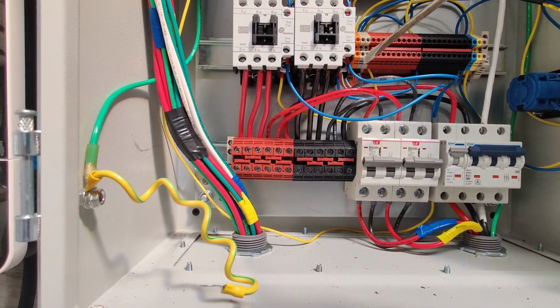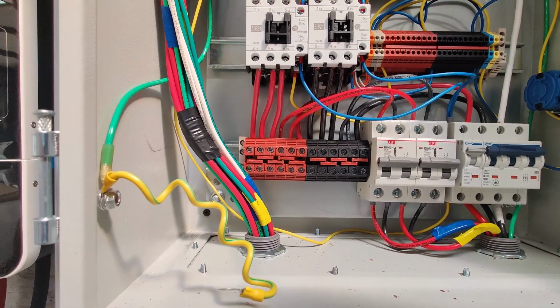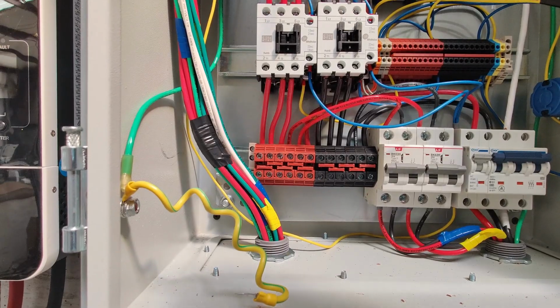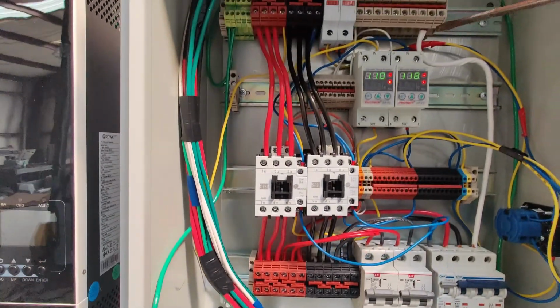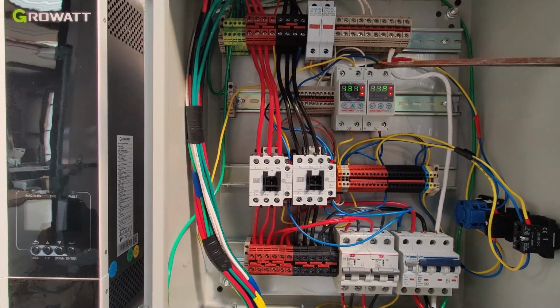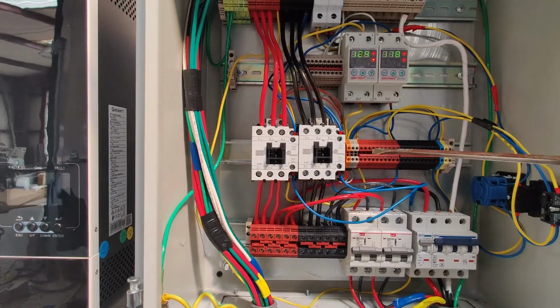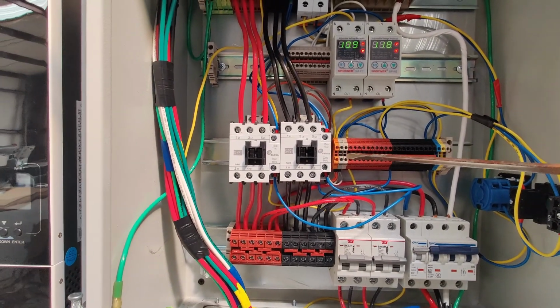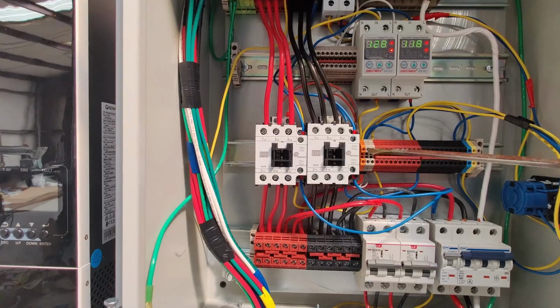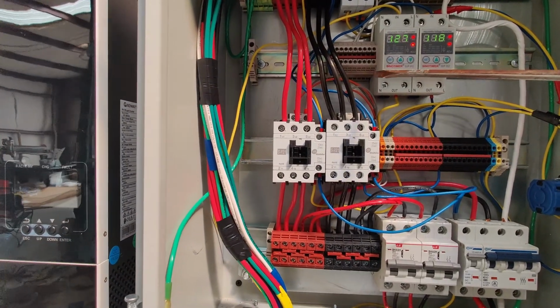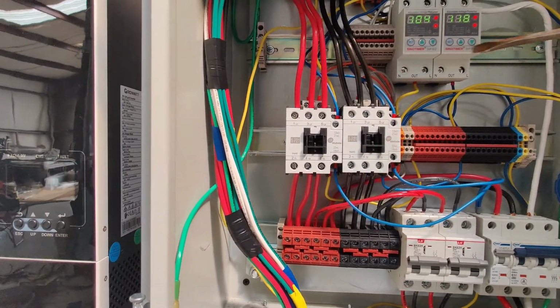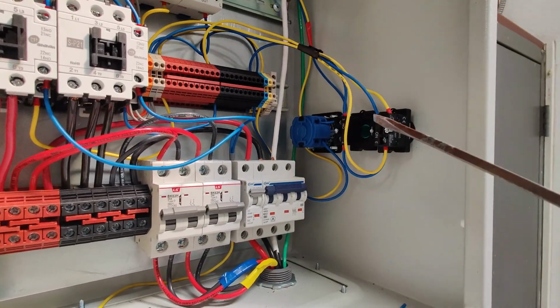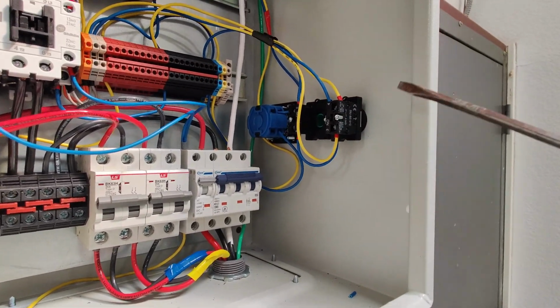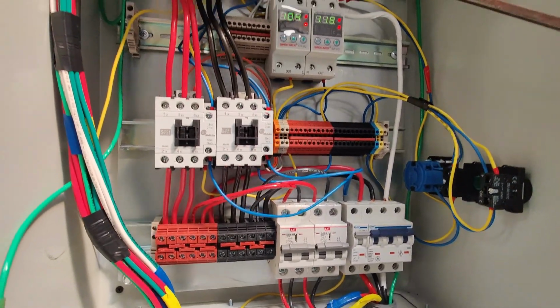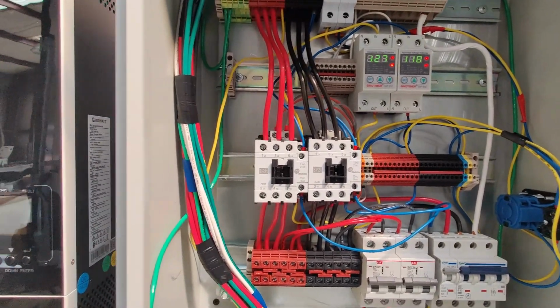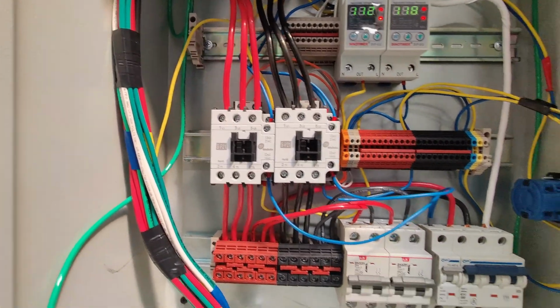They go through the normally open side of the contactors. They come up out of the normally open side of the contactors into each of the voltage protectors. Out of the voltage protectors into this orange and gray rail, and they come out of there and into the top side of the contactors. At the same time, we also have our momentary bypass switches, which follow the same current path but allow us to bypass the voltage protection relays to activate the system.